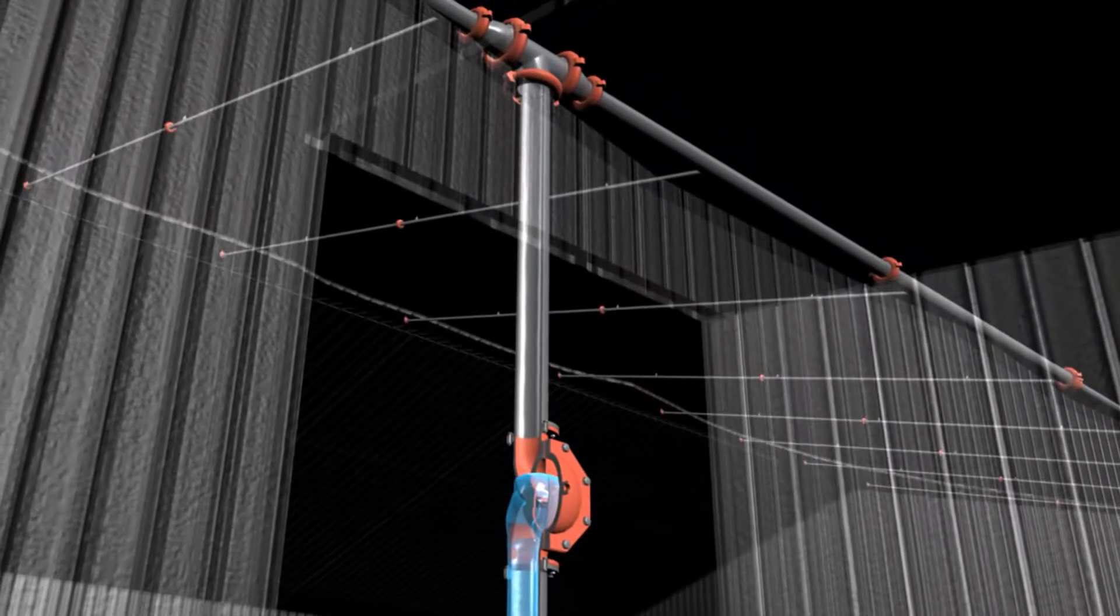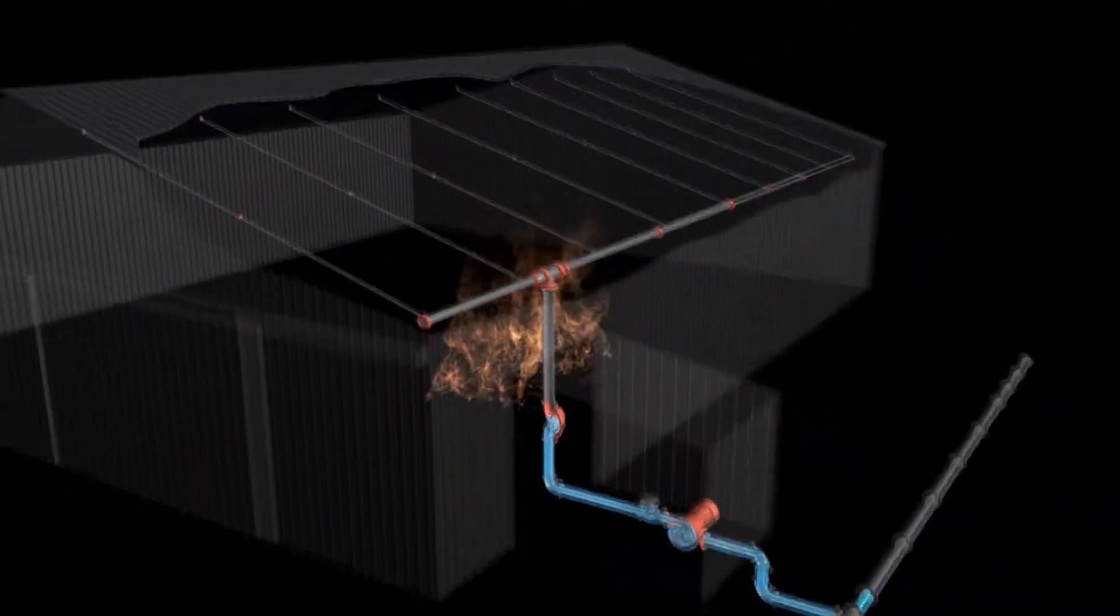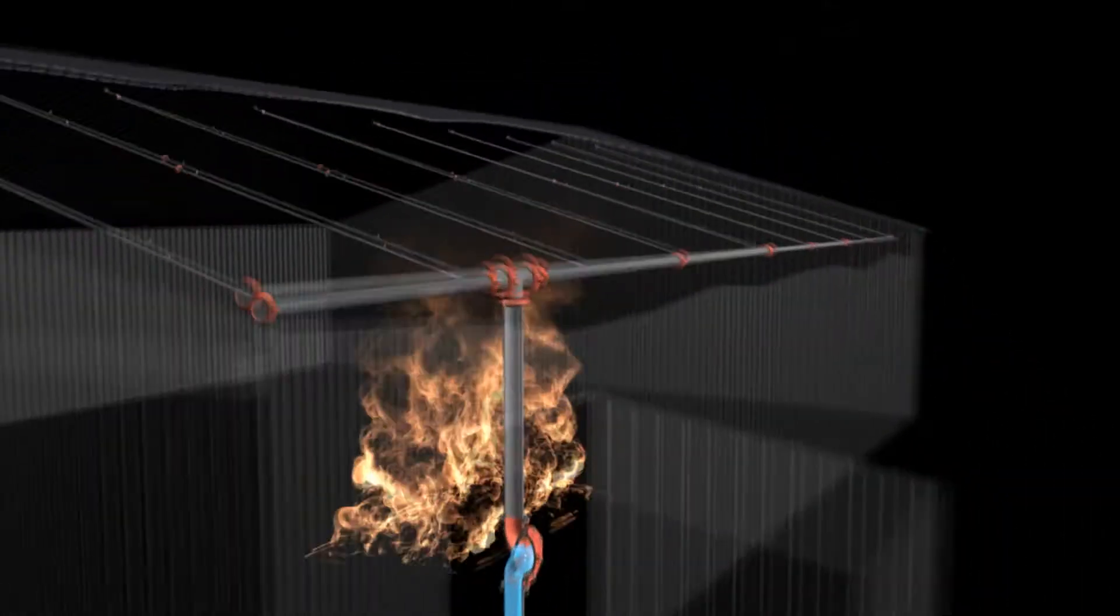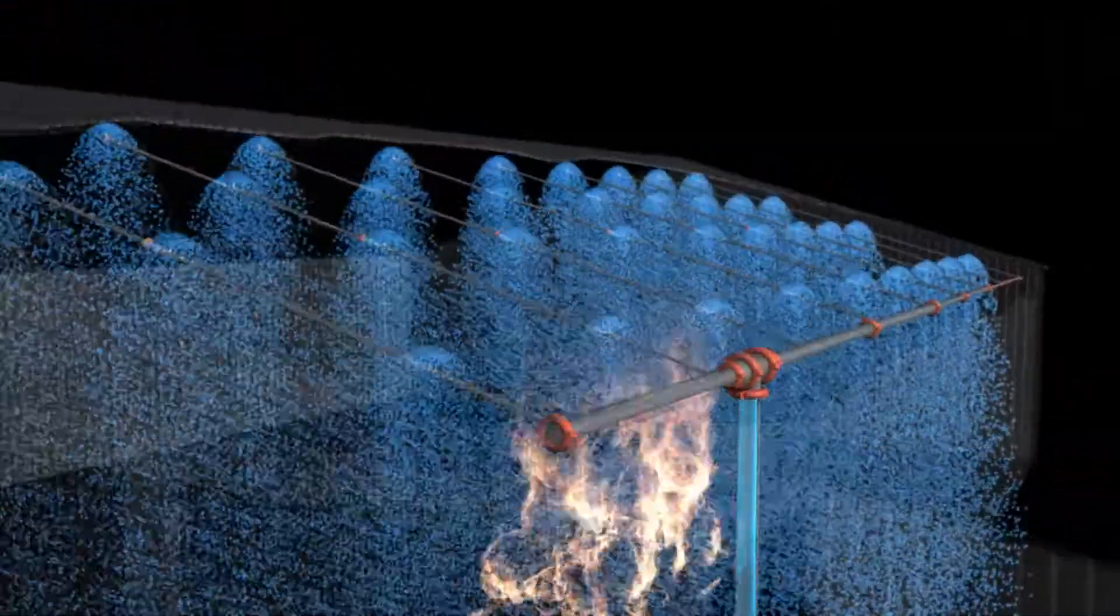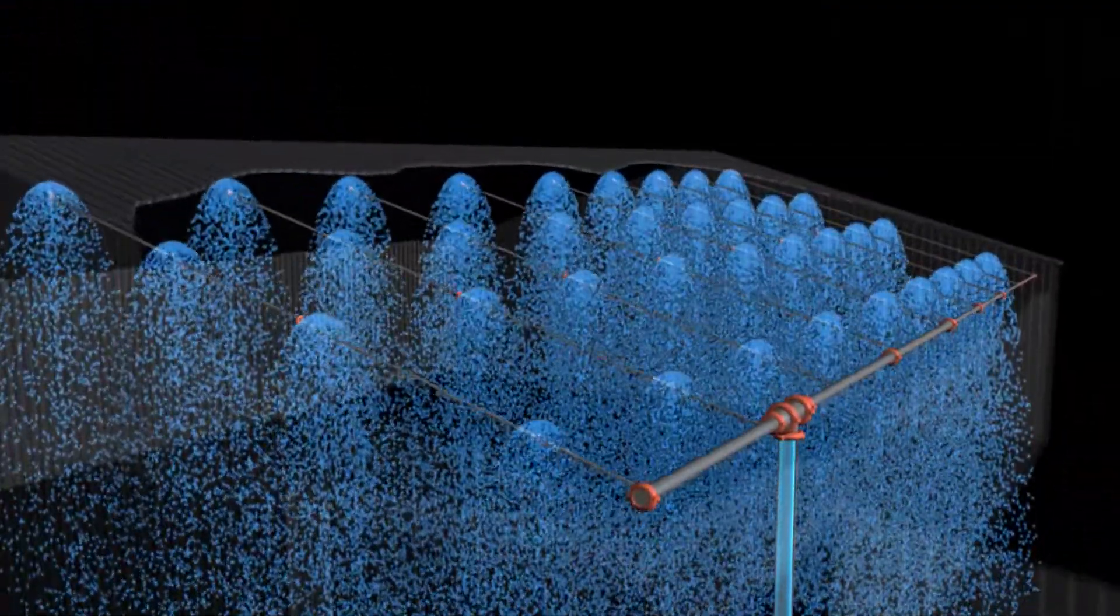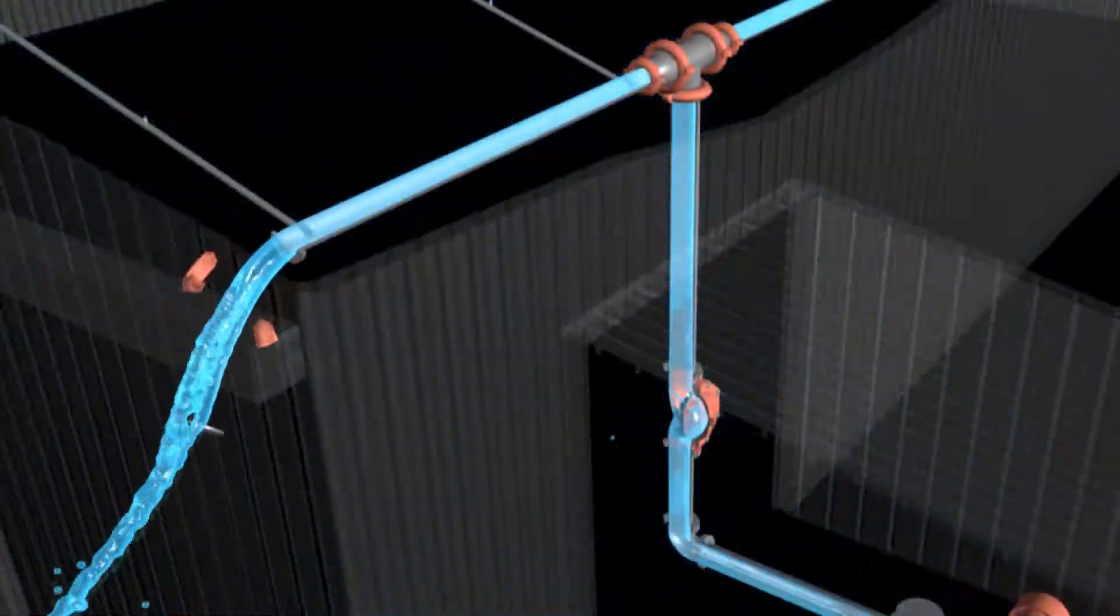When a fire occurs, the deluge valve opens and water is supplied to the heads under water main pressure. The sudden opening of the deluge valve can create a surge condition that can cause a sprinkler head or fitting to fail.